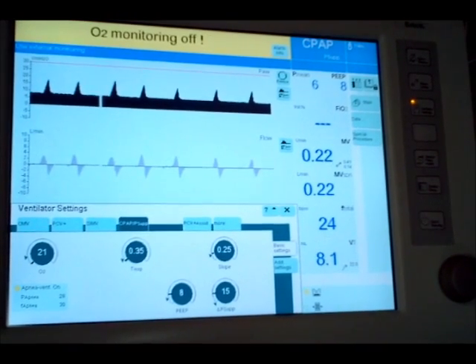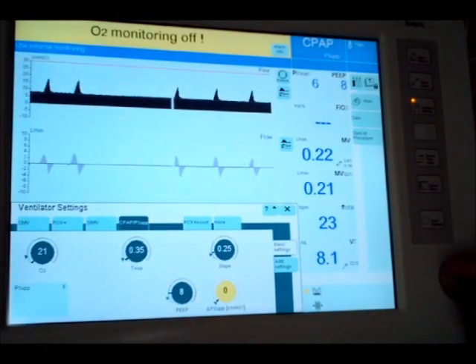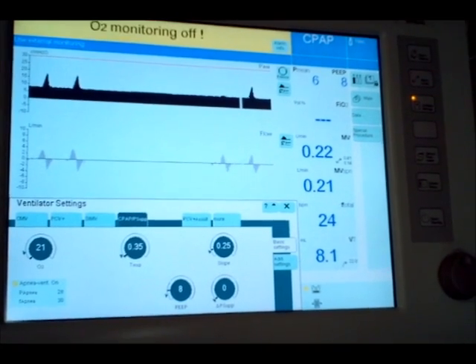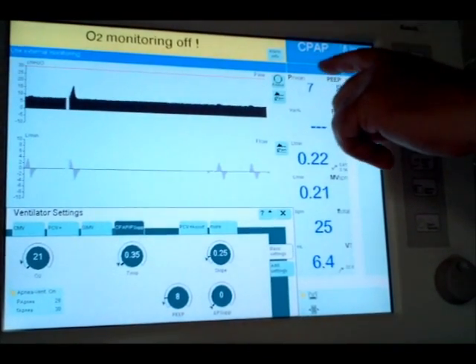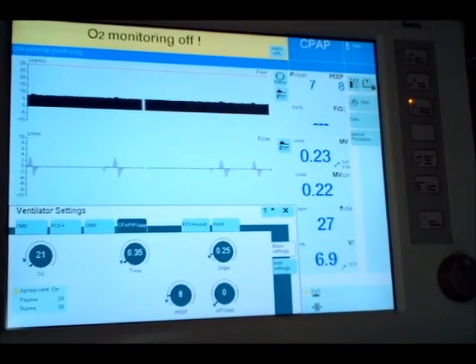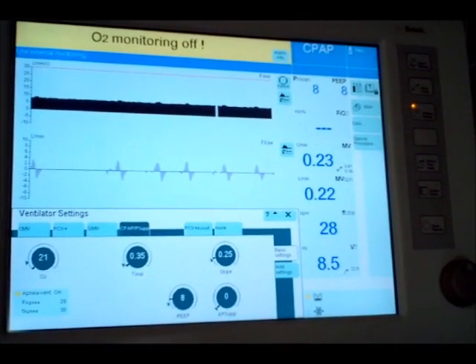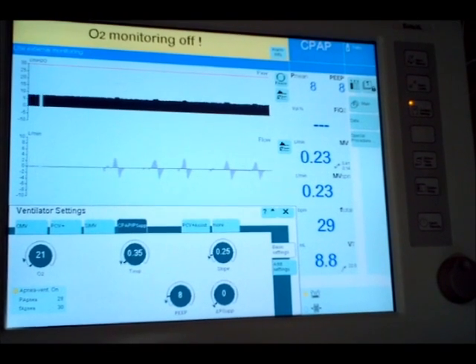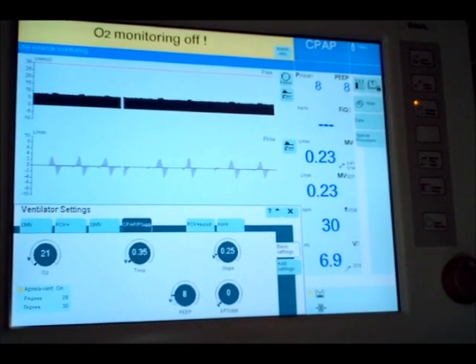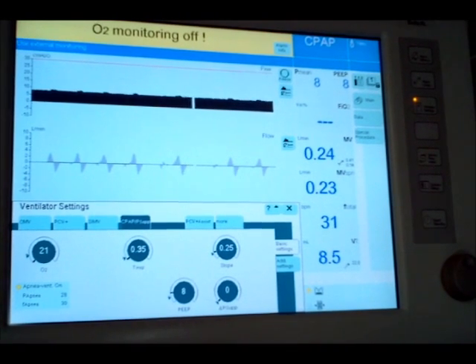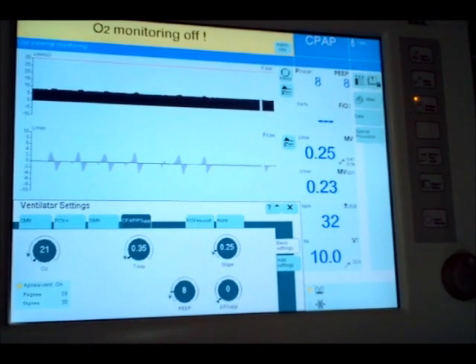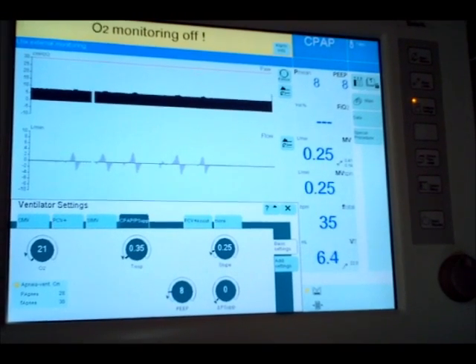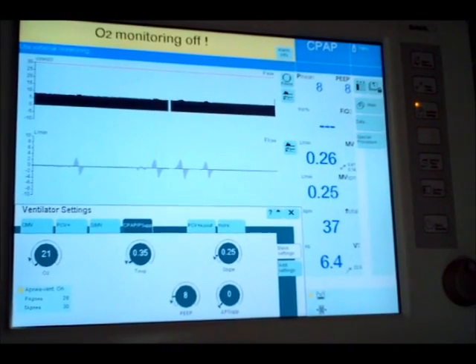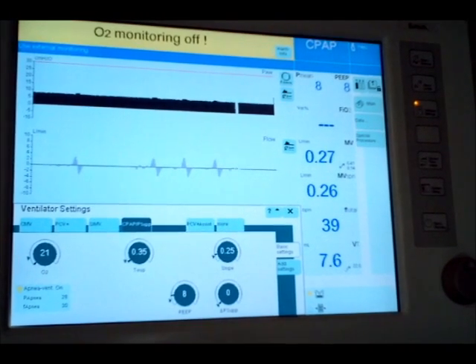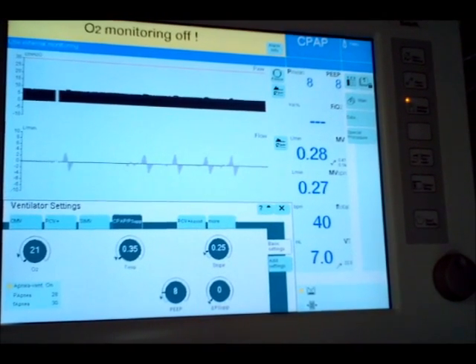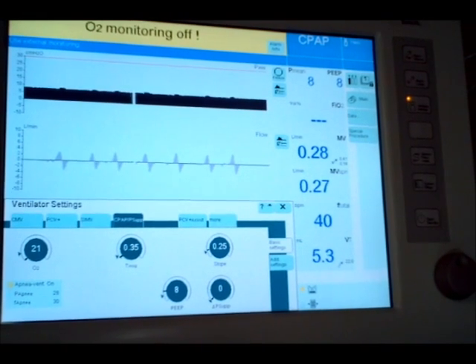I want CPAP, I don't want pressure support, so I turn my pressure support off. And I don't know if you noticed, but up here the thing that said pressure support also went off. So now we're in true CPAP mode. On this ventilator, you select the same mode for both CPAP and pressure support. So we really didn't change the mode per se. The key there would be B, where it says dial pressure support to 0 and adjust the CPAP level.